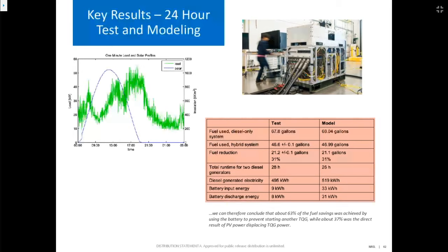The column here titled 'model' indicates that we did a completely offline model of this system, modeling as closely as possible all the components and decision making of the cube to predict what it would do in this particular scenario with this load profile. It used REOPT, another NREL modeling tool that's well received in the community. The model predicted this extremely well, only a tenth of a gallon off from how the cube actually performed in the field, and we validated that with this field performance.